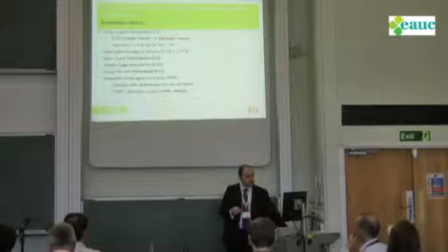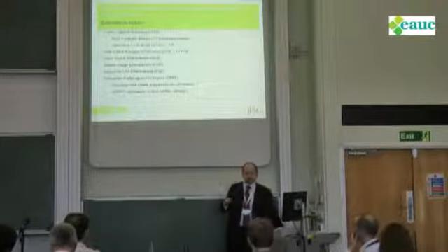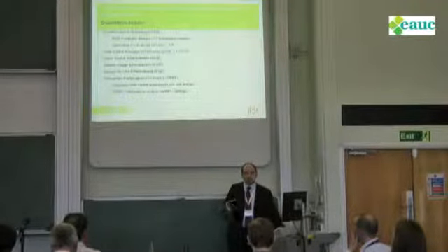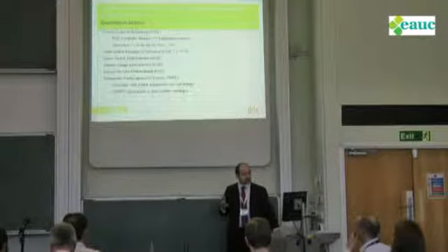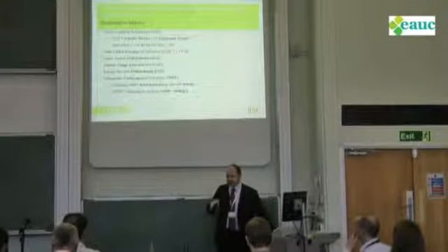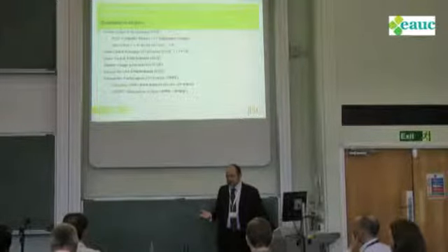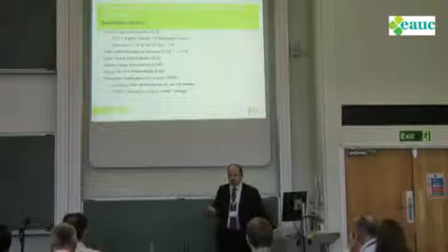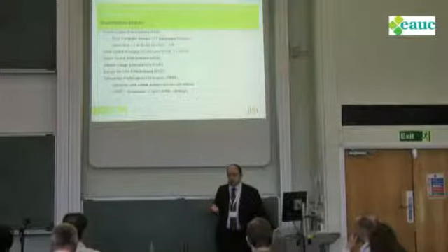And then, because measuring how effectively you use the power in your facility is a very crude measure, what they've tried to do with data center performance per energy metric is to say, well, what's the useful work that you're actually doing? Because you can have a server on doing nothing, and it's using 80% of its peak power. So that doesn't tell you that you're using power efficiently. In fact, quite the reverse. You're actually using it very inefficiently.